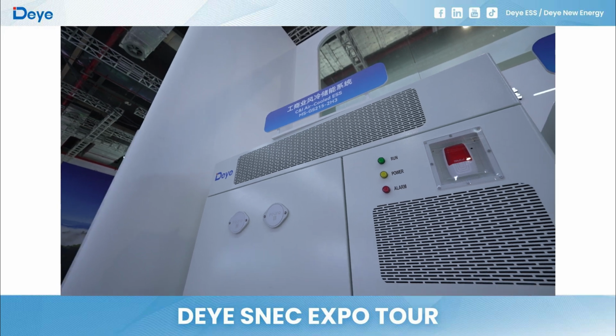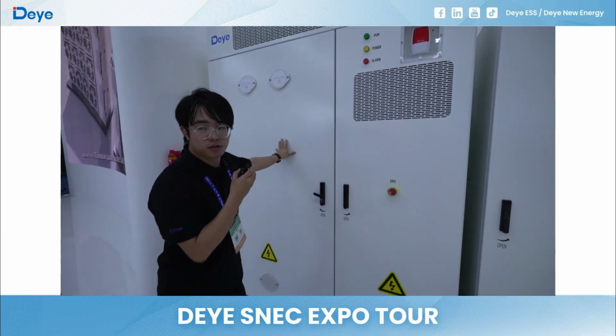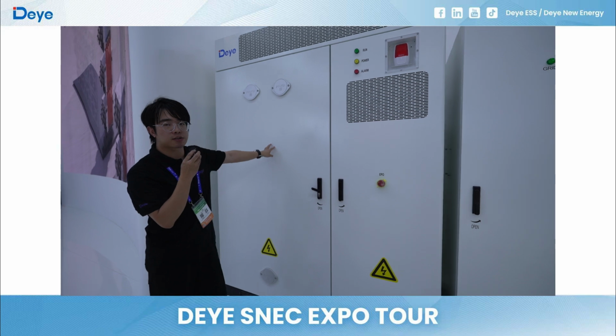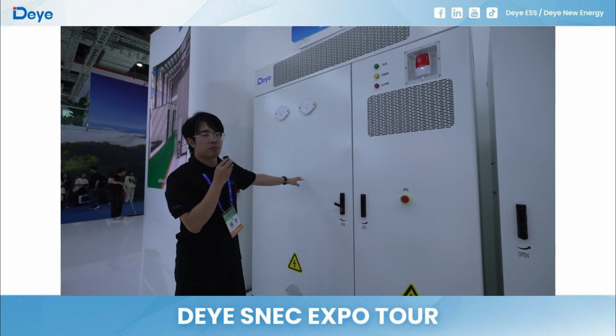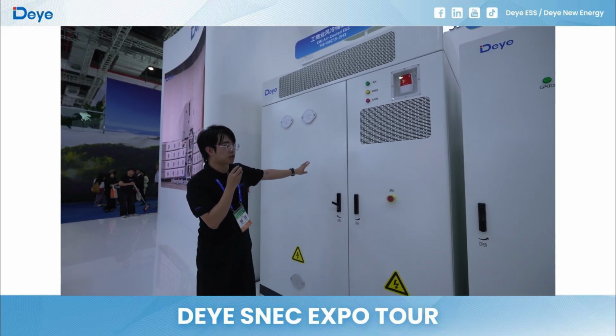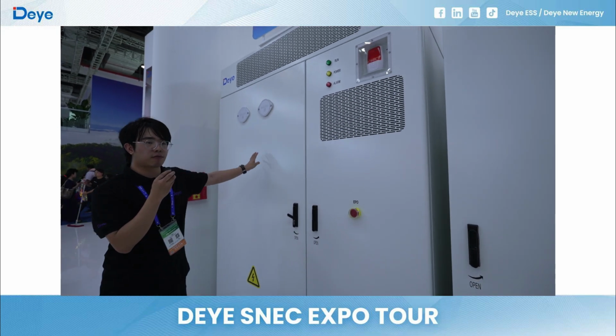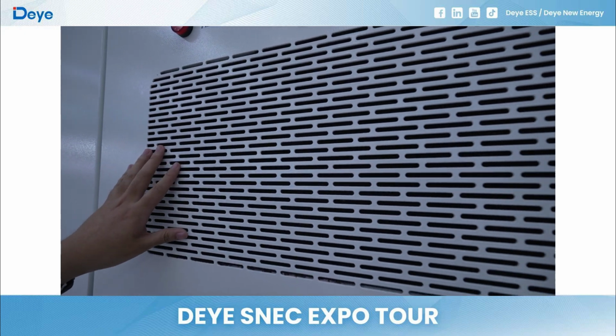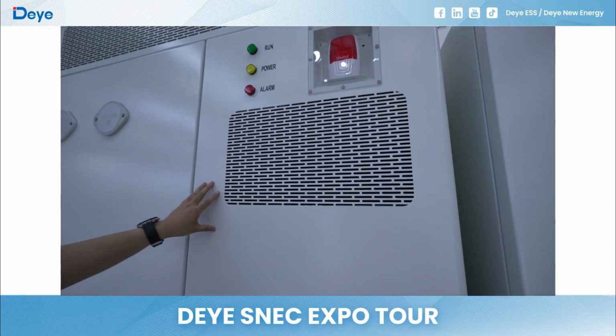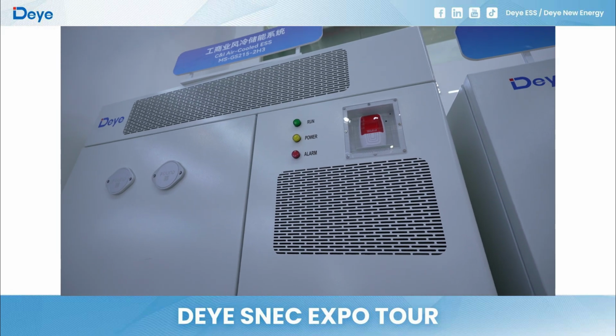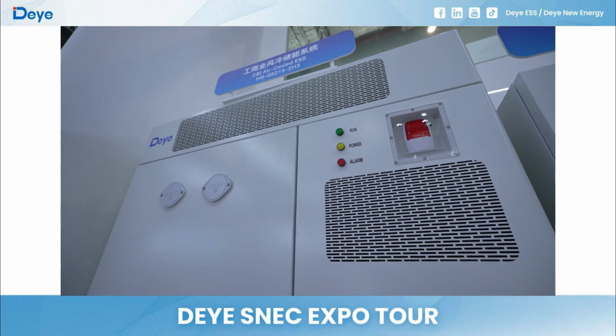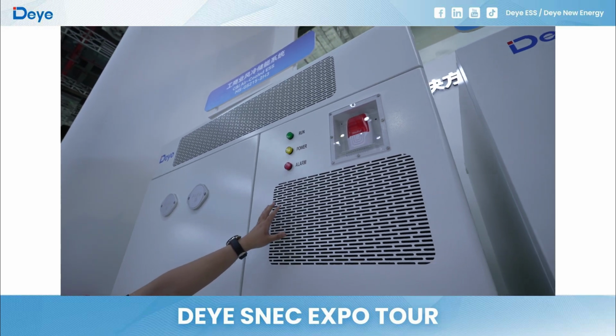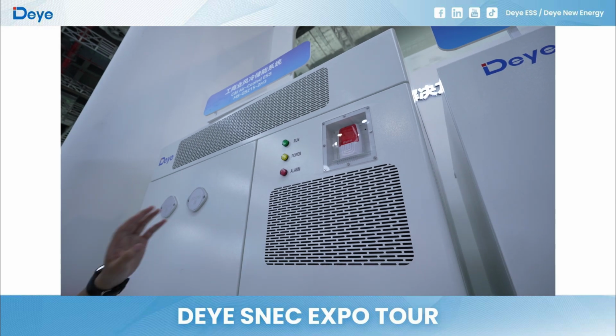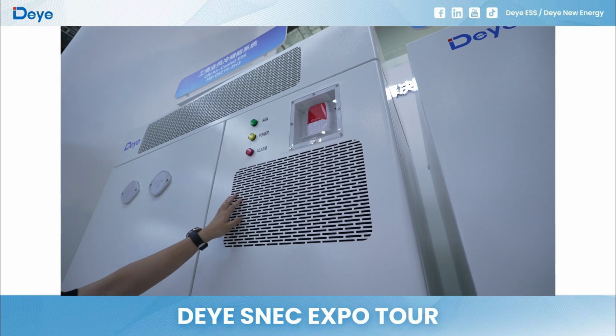Inside this cabinet there are 15 battery packs, each with an energy of 14 kilowatt hours, reaching a total capacity of 215 kilowatt hours. The inverter, the PCS here, is 100 kilowatts. So this cabinet is 100 kilowatts to 215 kilowatt hours, reaching about 2 hours of application. For the photovoltaic input, we can support a maximum of 200 kilowatts of photovoltaic power input.